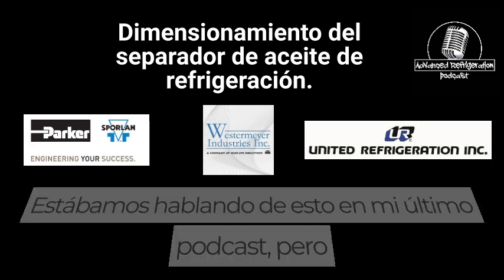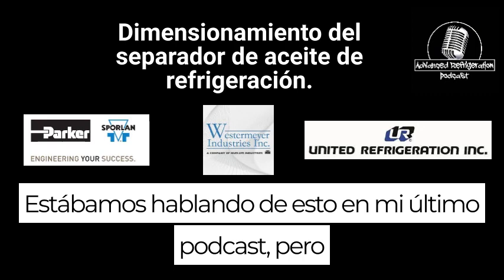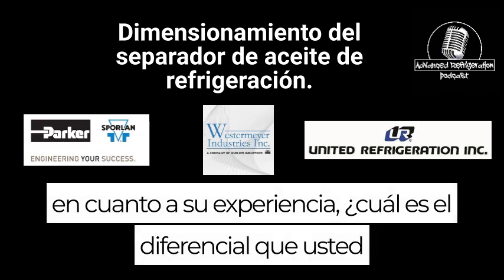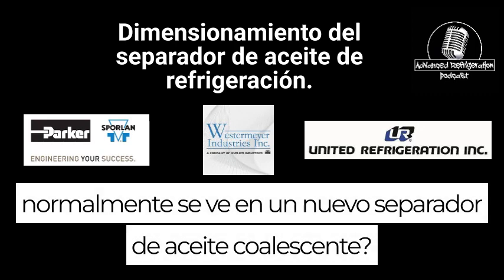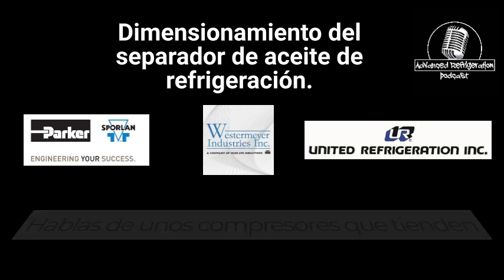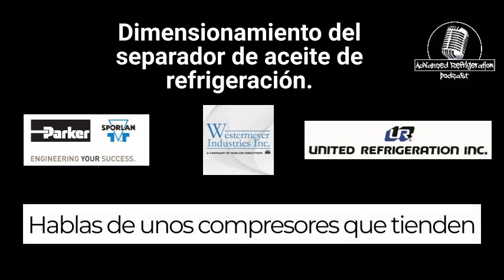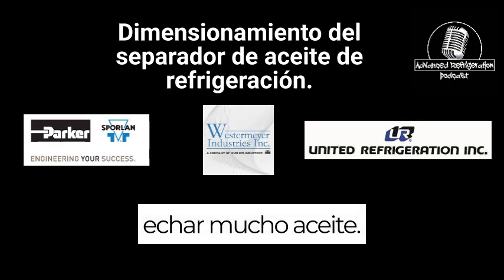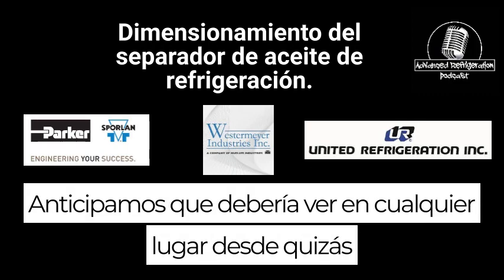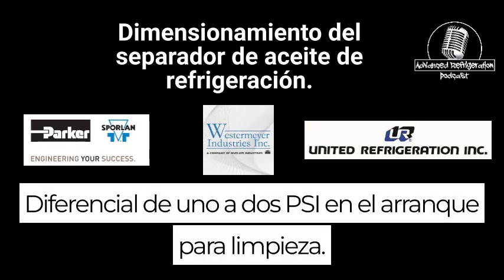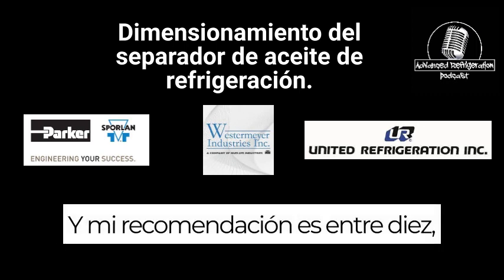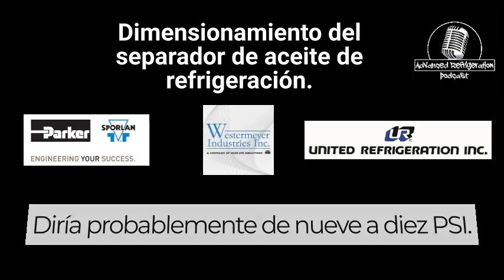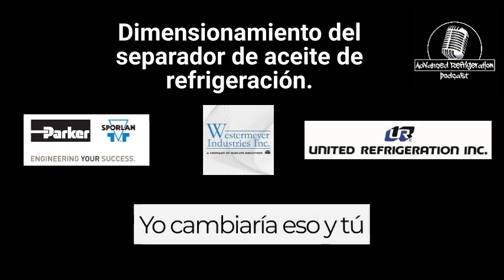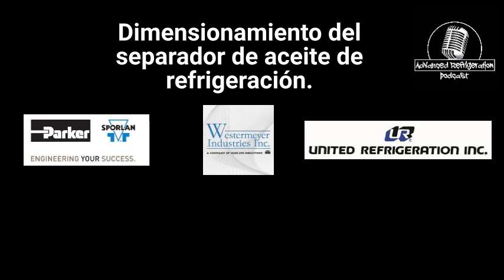We were talking about this on one of the last podcasts, but as far as your experience, what's the differential that you typically see on a brand new coalescing oil separator? You talk about some compressors that tend to throw a lot of oil. We anticipate that you should see anywhere from maybe 1 to 2 psi differential on startup for clean. And my recommendation is, I'd say probably 9 to 10 psi, I'd get that thing changed, or you're going to end up with a problem.